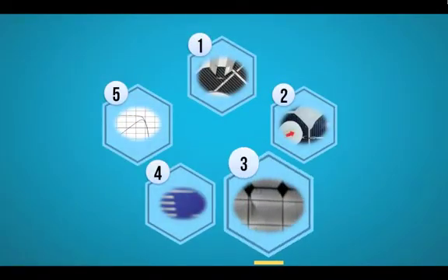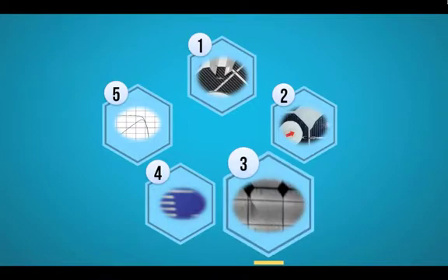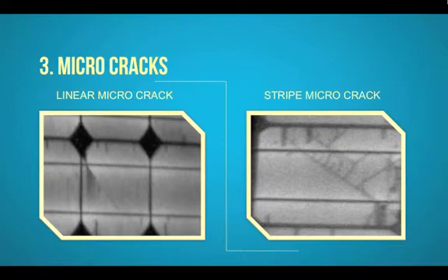Micro-cracks are the third most common quality problem, and this is quite a serious and impacting issue. Many manufacturers do not pay enough attention to micro-cracks. Most micro-cracks are a result of mechanical forces or thermal stress, and they most frequently occur during lamination of the panel or during soldering. During manual soldering, different thermal expansion of the copper and silicon elements can occur at temperatures greater than 300 degrees, resulting in micro-cracks and higher cell resistance. Undetected, micro-cracks can result in a less-than-expected field lifespan.